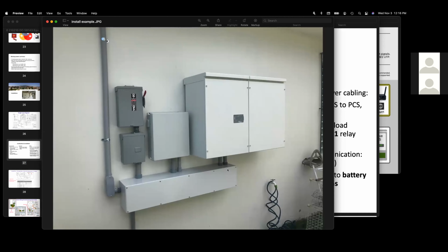What Luke is talking about here is the gutter and oversizing the nipples in the installation. So these kind of oversized conduit runs. You could probably do the one back and forth to the battery cabinet into the gutter with one larger size conduit. And then that way you've got this entire gutter to do all of your back and forth wiring with. And then you'd have one home run conduit effectively over to the main service panel. And that's exactly what Luke's talking about here. Thanks again, Luke. Appreciate that comment.